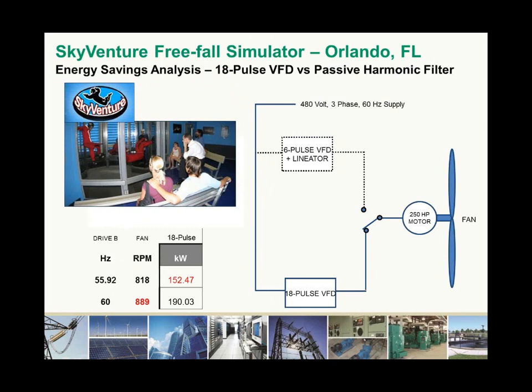At another site in Orlando, Florida, a demonstration was done to further highlight the energy savings potential of the passive filter. At this site, an 18-pulse drive was initially adopted. And by switching between the 18-pulse and the 6-pulse VFD with our Lineator filter, we could compare the energy consumption of the 2 solutions. With the 18-pulse shown here, running at 60 hertz, fan speed of 889 RPM, the single 250 horsepower fan was drawing 190 kilowatts.